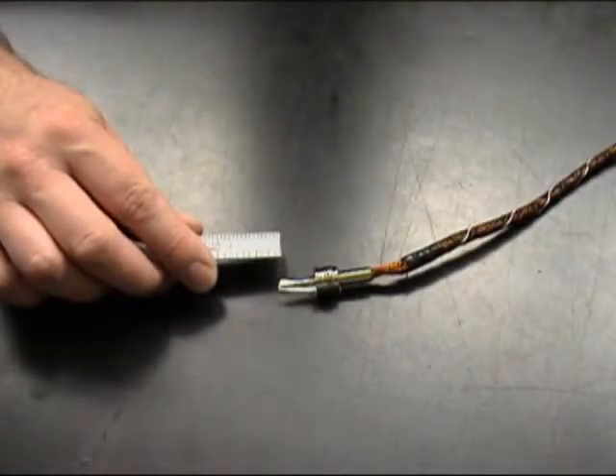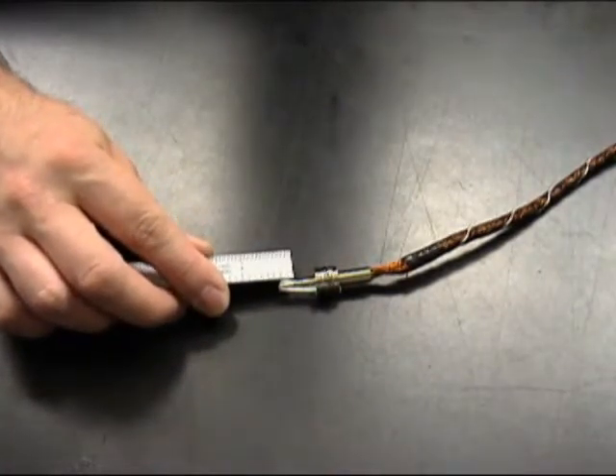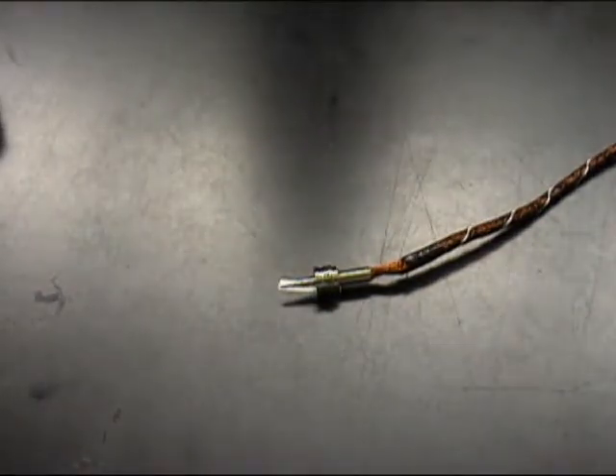Now we're going to check to see that we have three eighths of the wire ferrule sticking out past the end of the pin — that's not counting the wire sticking out of the end of the wire ferrule, just the wire ferrule itself. In this case we only have a quarter inch so we'll need to remove more of the shield wire.